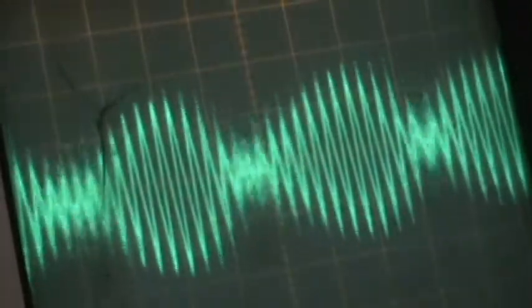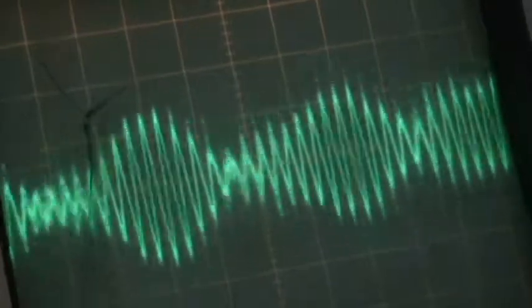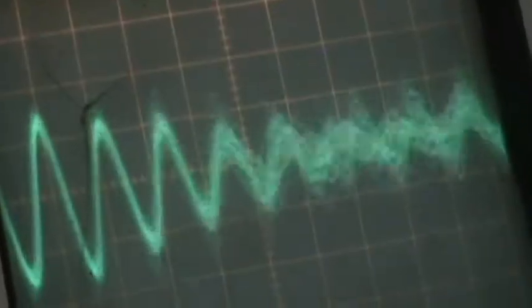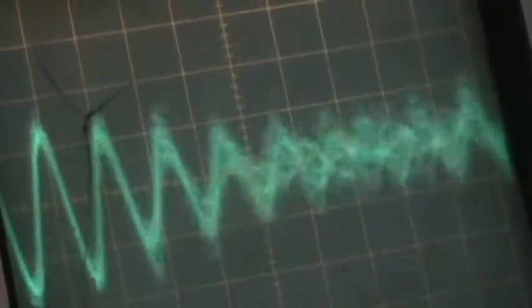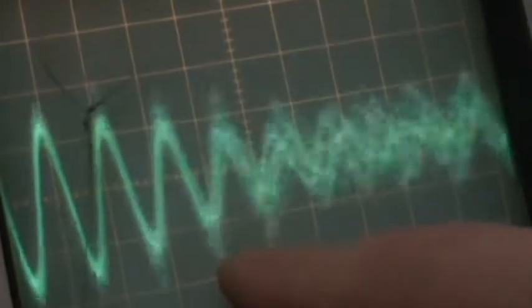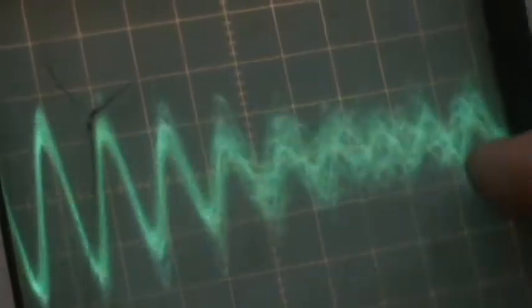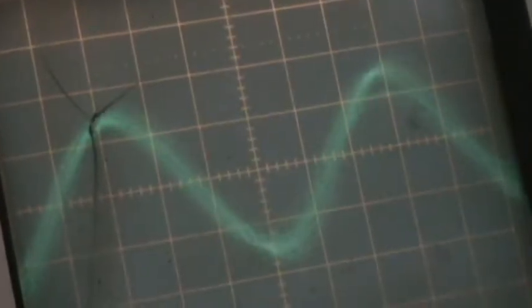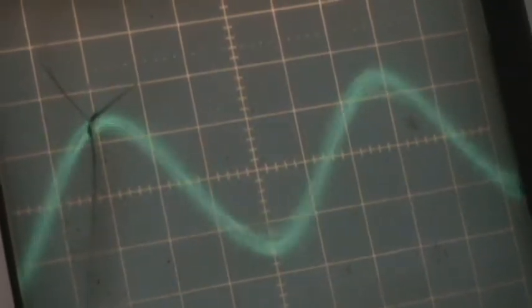So there's a frequency within a frequency there. Let me show you a few more, let's zoom in on this. Okay, we're gonna change our sweep time division. Seems like every other one is faulty on here, but there's the signal again. You can see it gets very big, getting small, actually bigger again, but it's off the camera. They're zooming in more. And you can see the frequency is flickering all over the place.